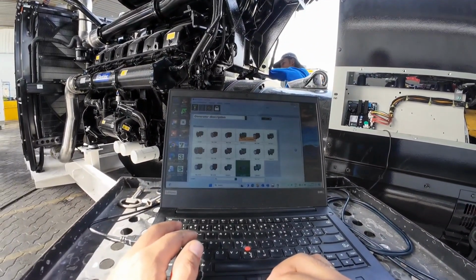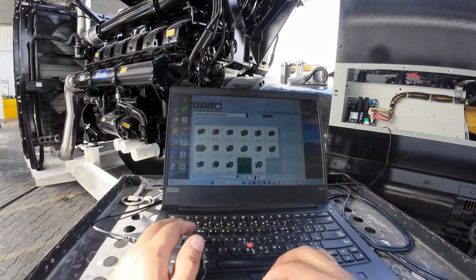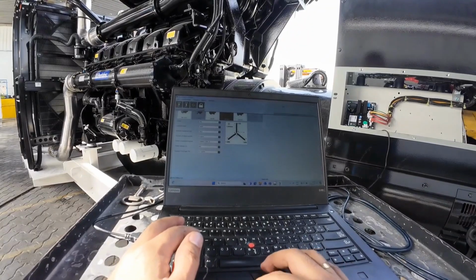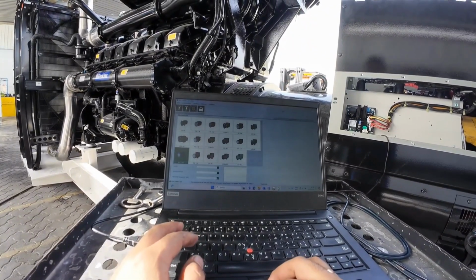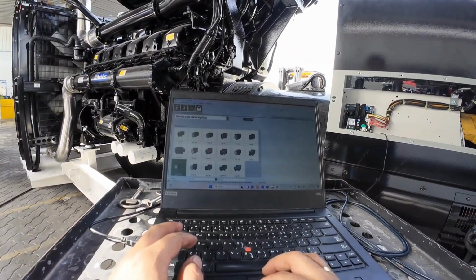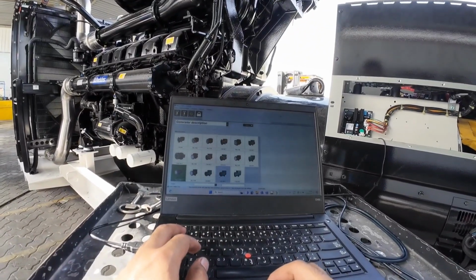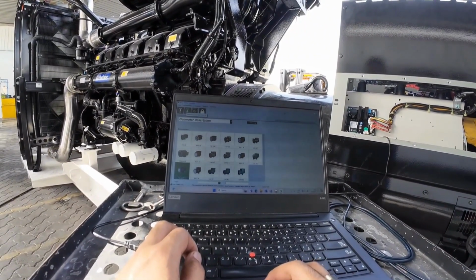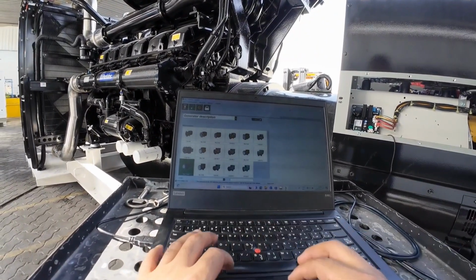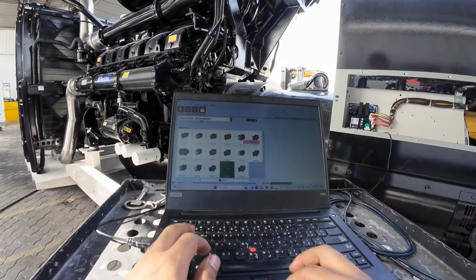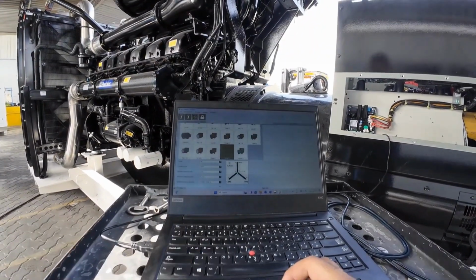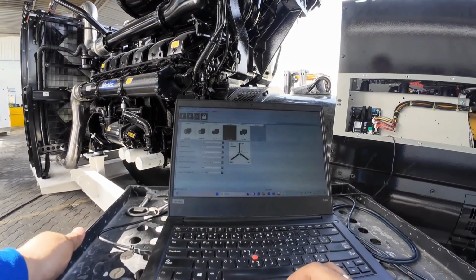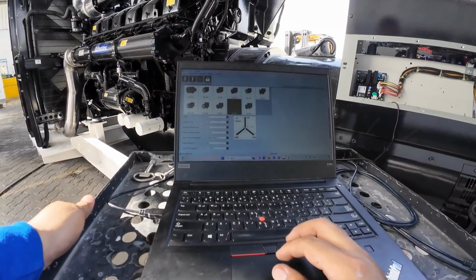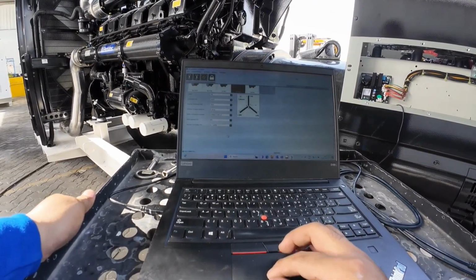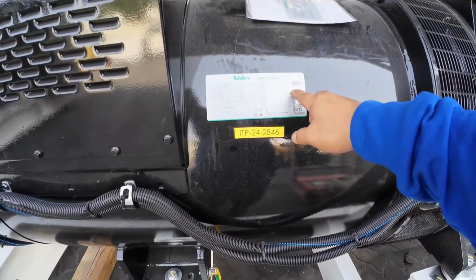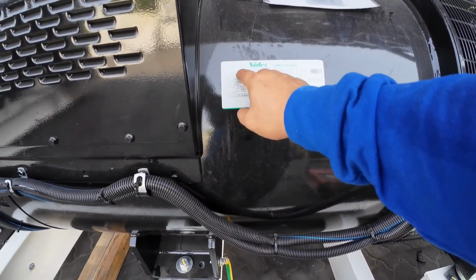I'm starting to configure the AVR. If you are doing the configuration for the AVR, make sure you check the nameplate for the alternator so you can correctly configure this type of AVR, because the nameplate states what type of alternator it is and what the connections of our alternator are. This lets you do the configurations for the maximum excitation and voltage output this generator must have.